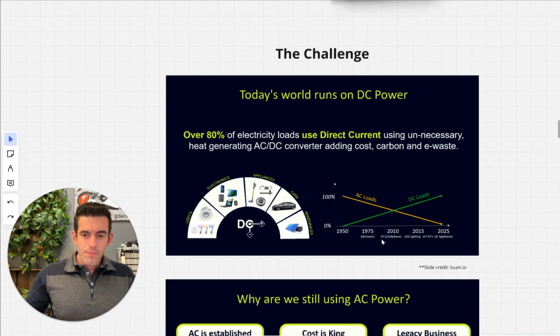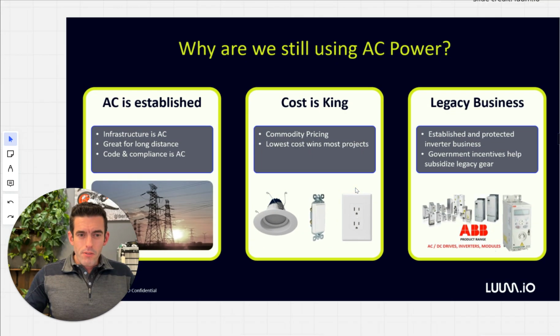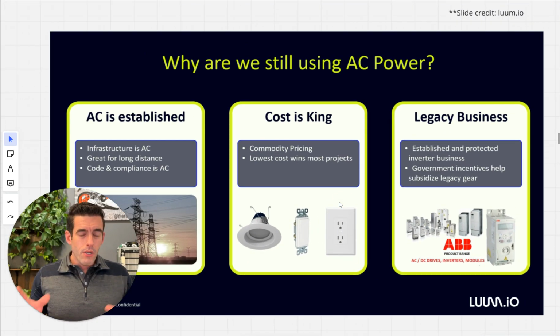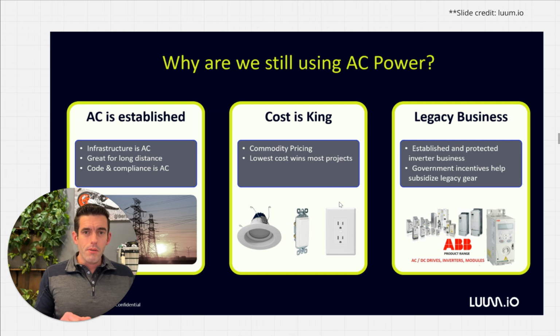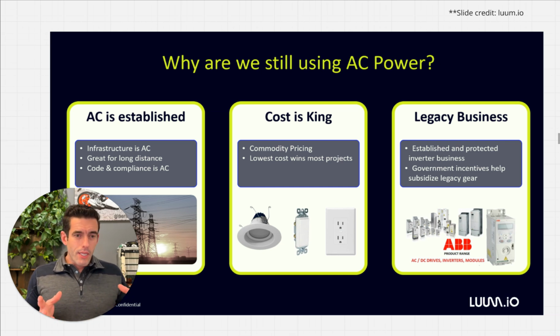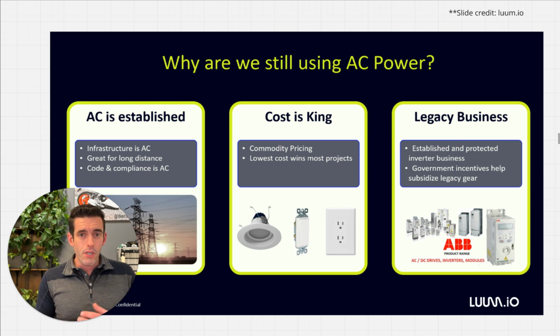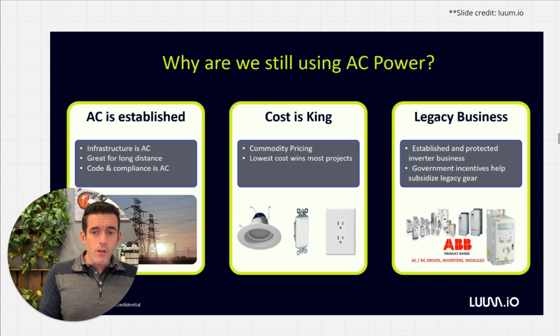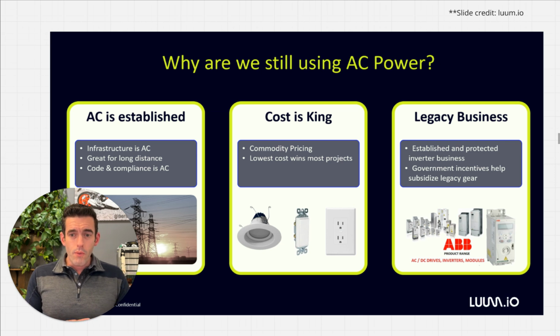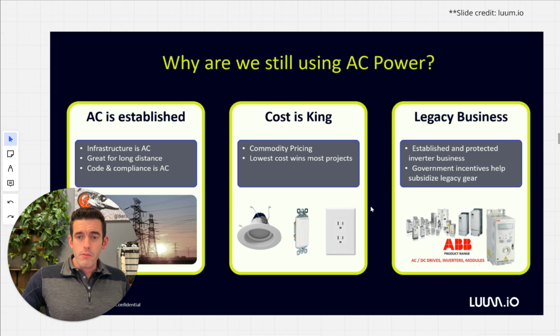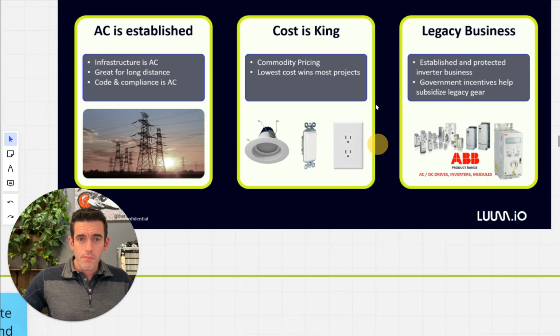The challenge though is, why are we still using AC power? Well, it's because at the time it made sense. When it first came around, AC was the better way to move energy long distances. That's very well established and understood, and that's where most of the National Electrical Code has focused for quite some time - the AC voltage. It wasn't until the very recent code revision cycle, specifically the 2023 NEC code update, that we started getting better guidance on DC voltage. The cost has been a lower cost solution to be AC for quite a while, and most of the big legacy players are predominantly around the AC voltage side of the industry.